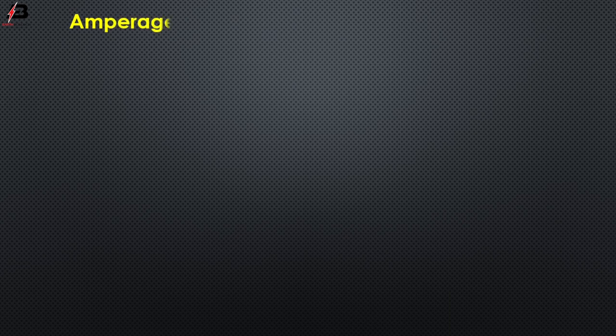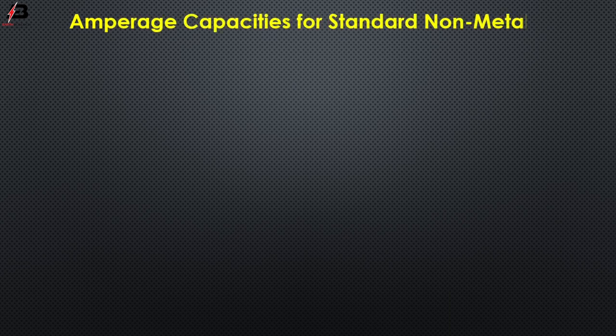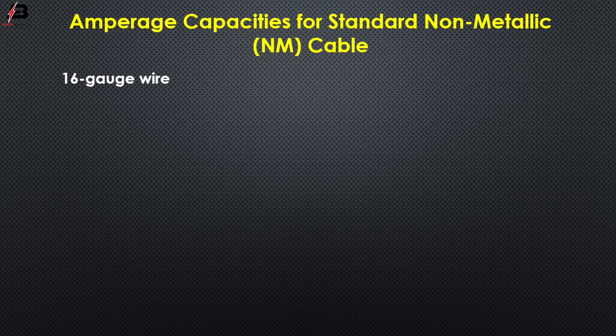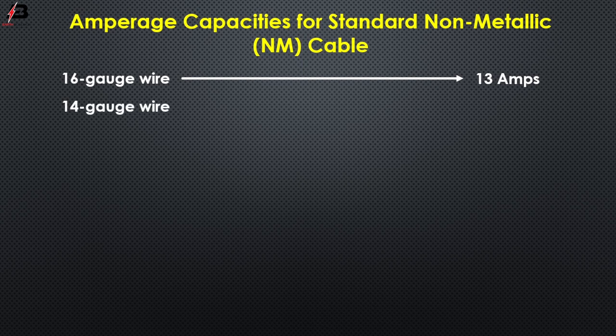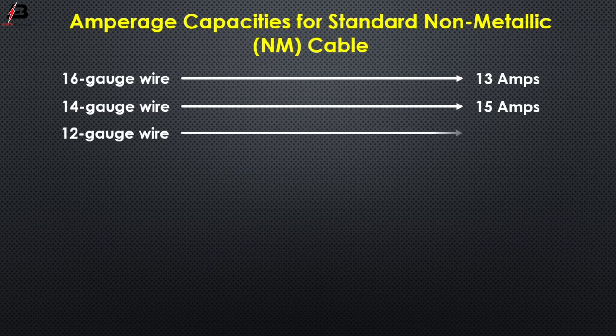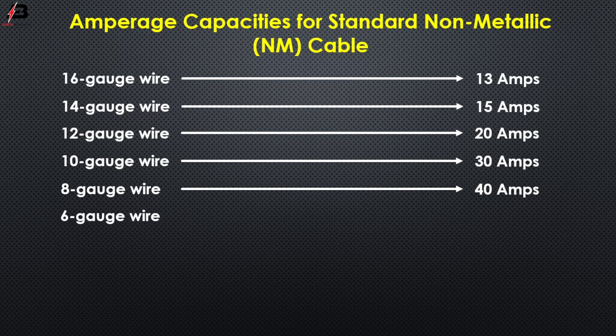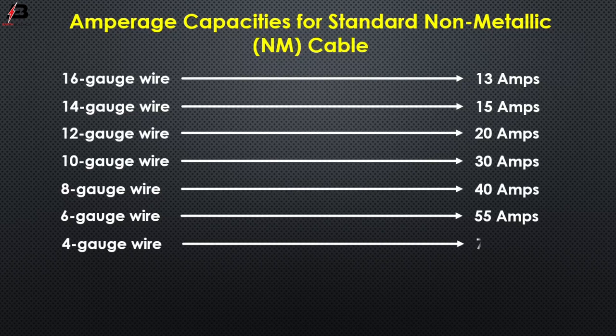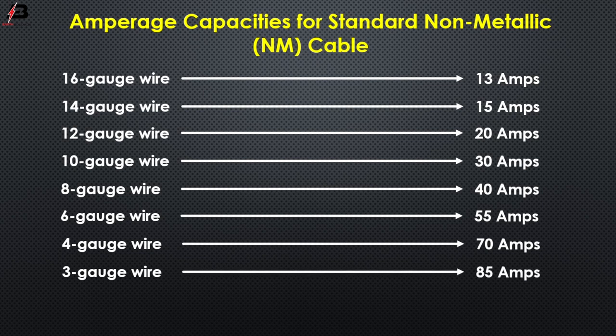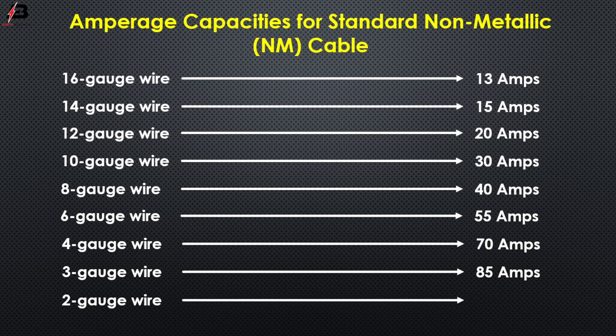For standard non-metallic cables, the ampere capacities are: 16 gauge wire — 13 amperes; 14 gauge wire — 15 amperes; 12 gauge wire — 20 amperes; 10 gauge wire — 30 amperes; 8 gauge wire — 40 amperes; 6 gauge wire — 55 amperes; 4 gauge wire — 70 amperes; 3 gauge wire — 85 amperes; 2 gauge wire — 95 amperes.